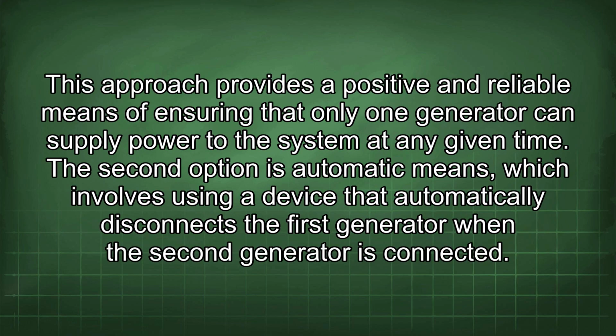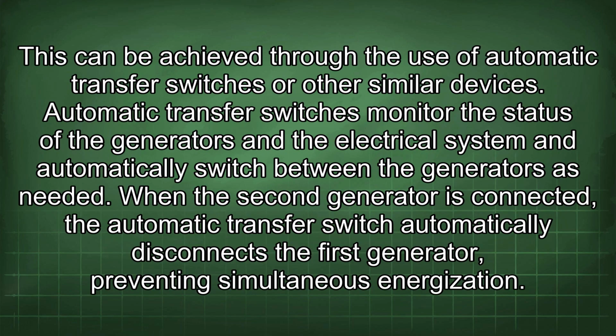This approach provides a positive and reliable means of ensuring that only one generator can supply power to the system at any given time. The second option is automatic means, which involves using a device that automatically disconnects the first generator when the second generator is connected. This can be achieved through the use of automatic transfer switches or other similar devices.